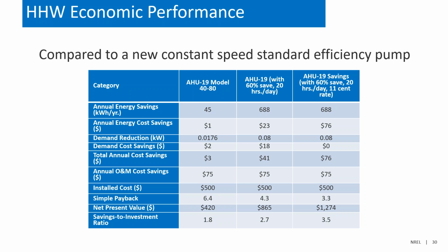system. We did run a couple of other scenarios where we were trying to match the runtime of AHU 19 to AHU 17, which was running about 20 hours a day. And we do think if you did have a 10 to 15-year-old pump in there, you still would see very substantial peak power savings in that case.